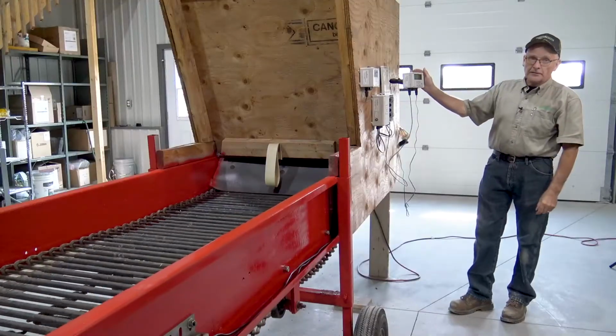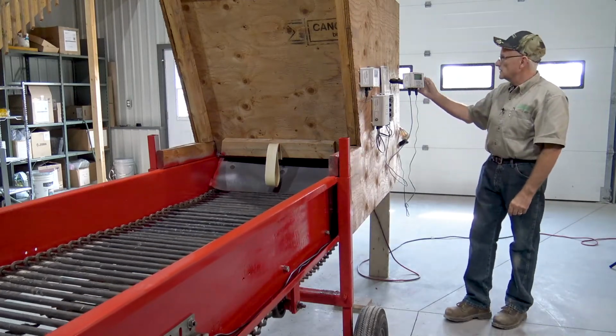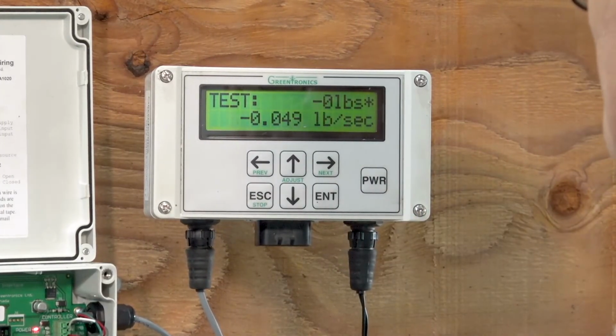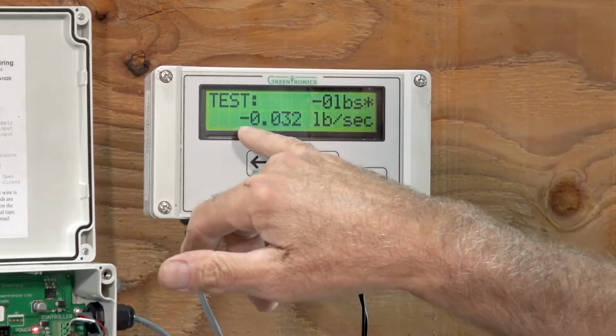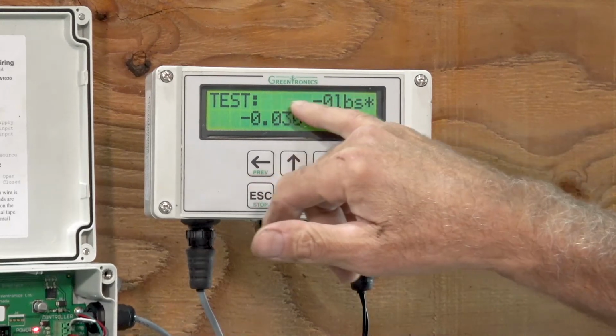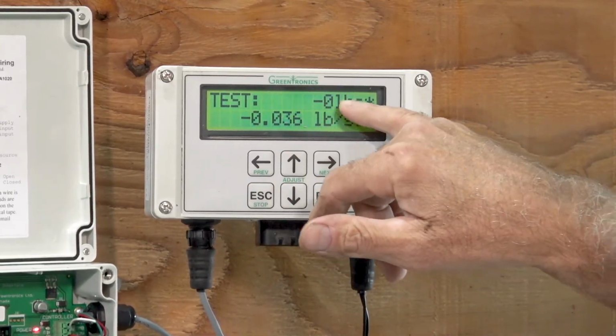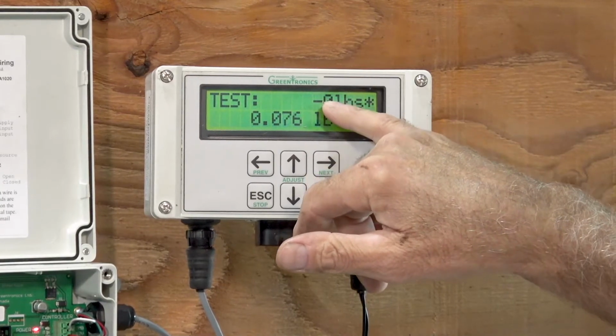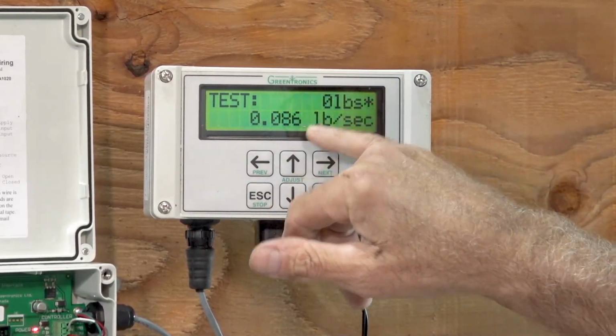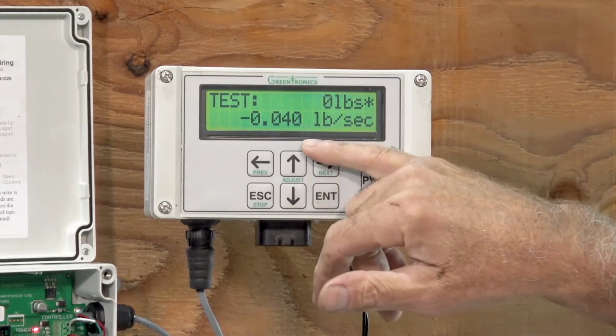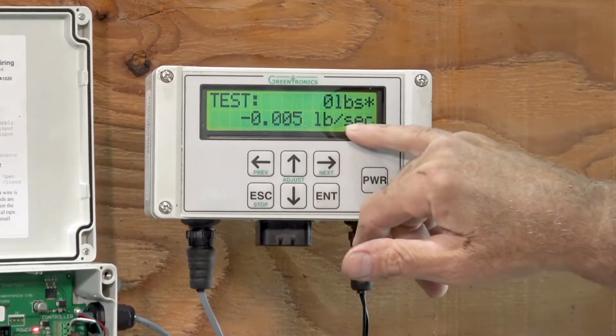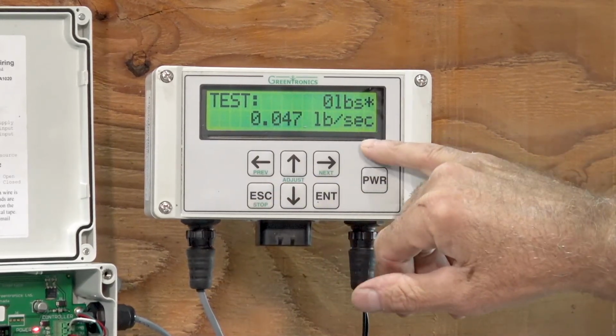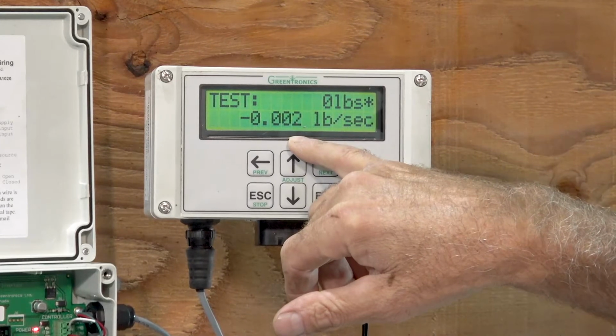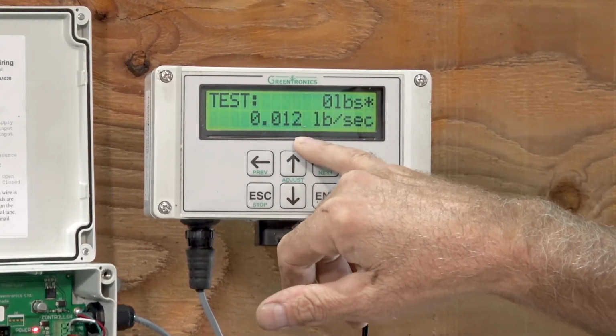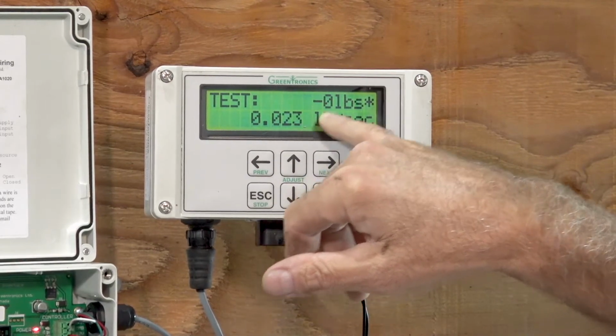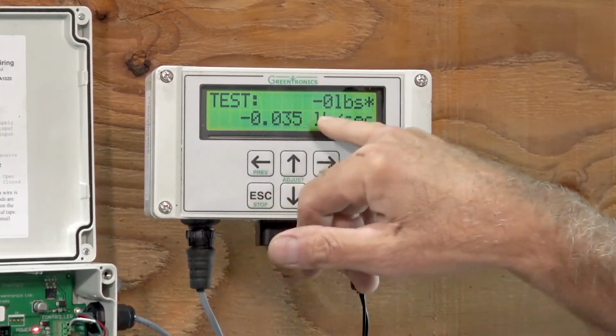Hit enter, and the very first one on here is test tare. So we'll hit enter. And what we want to see now is that our accumulating weight, our load weight for example, here stays 0. The belt is empty, it's running, but it should stay 0 because there's nothing on it. We see a little bit of an up and down number here. This is our flow rate in pounds per second. And it's bumping up and down a little bit, sometimes a little negative, then a bit positive. It's a very low number. We don't see any weight accumulating, so it seems to balance out to 0.